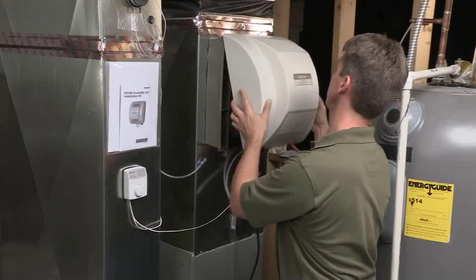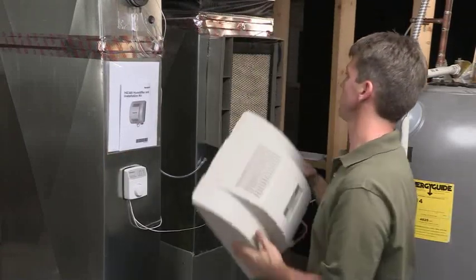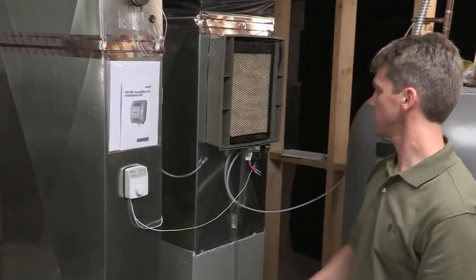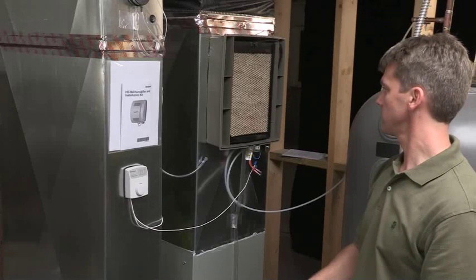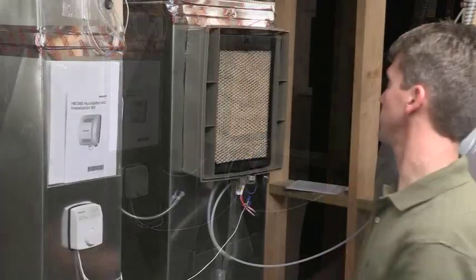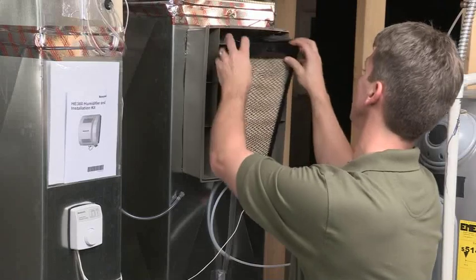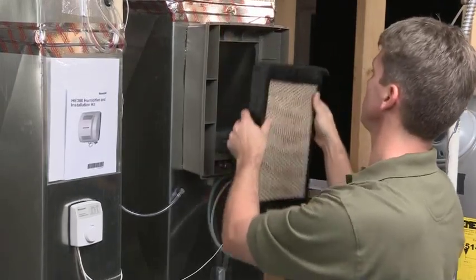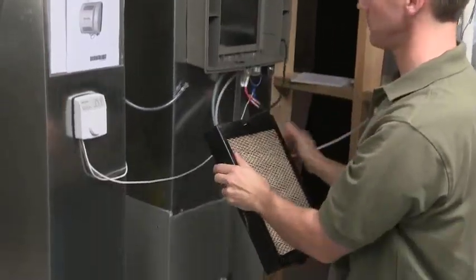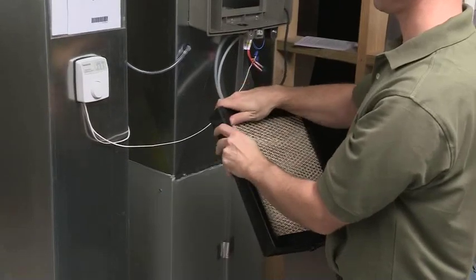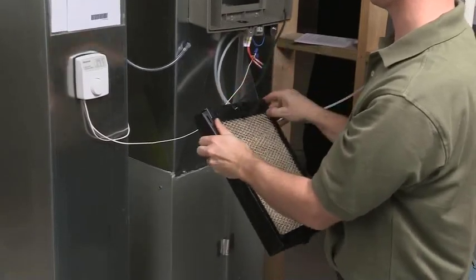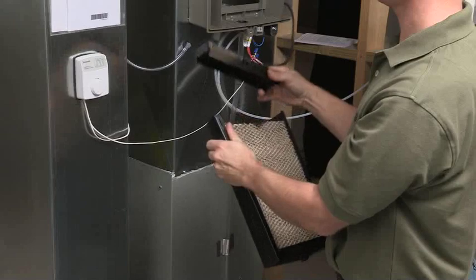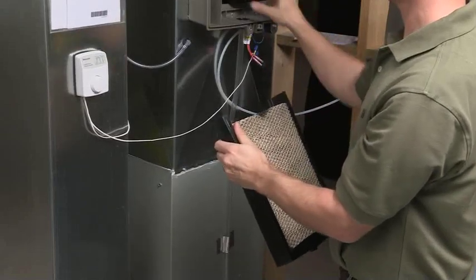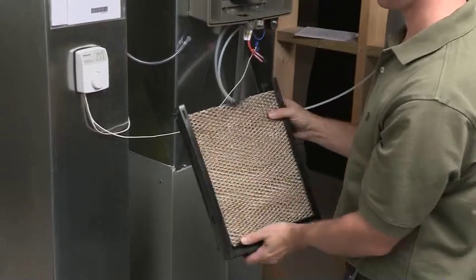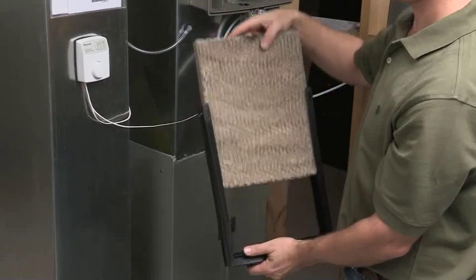Remove the humidifier cover by unplugging the connector and loosening the thumb screw. Grasp the cover near the bottom and pull it toward you. Then, remove the humidifier pad assembly by grasping the top of the tray and pulling it toward you. Remove the tray from the frame. Gently pinch the end of the water nozzle and lift it off the tray. Slide the humidifier pad out of the frame.